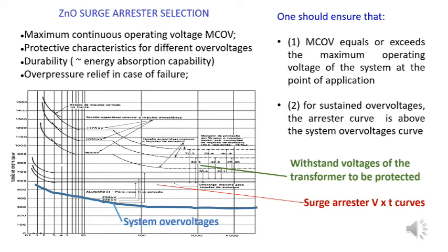And then above the curve of the surge arrestor, we have the curves of supportability, withstandability of the transformer or another equipment which is to be protected. In the black curve, in the upper part, we are showing for three different impulse levels a curve which represents the impulses and the applied voltage of longer duration that the transformer or other equipment can support.